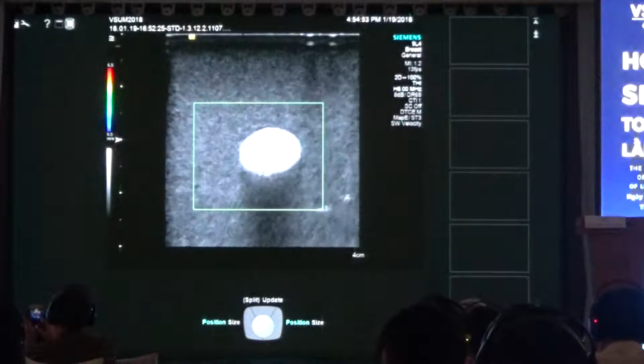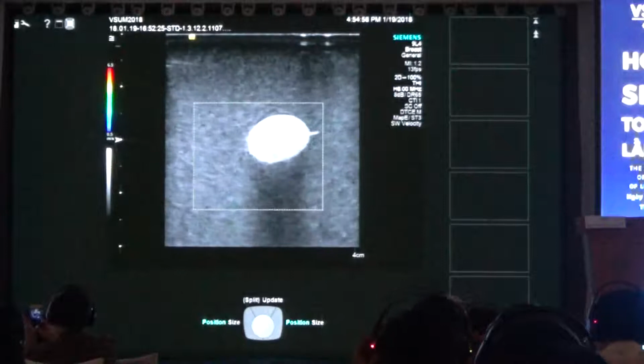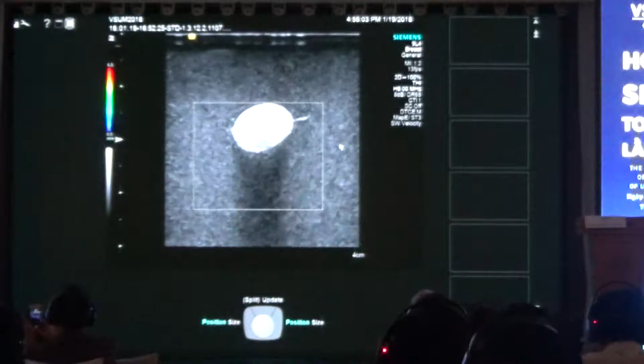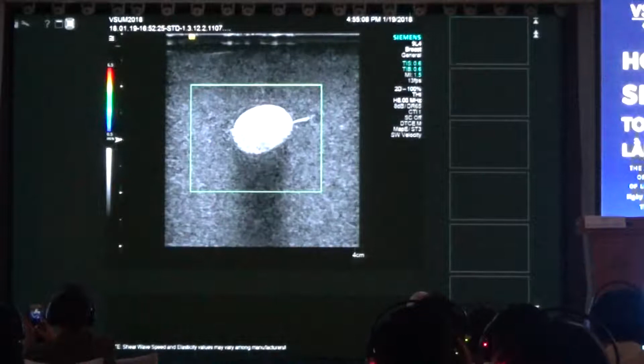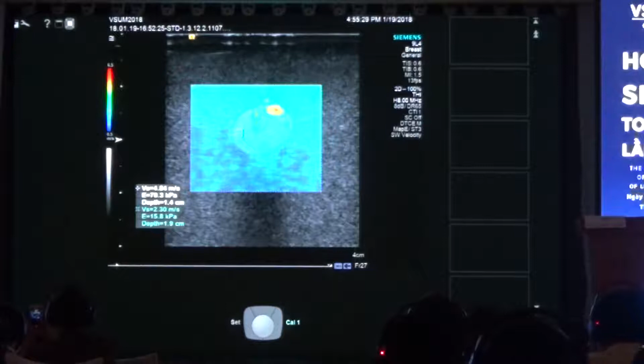Another problem we can have is if you don't apply uniform pressure. So what I'm going to do is on the right side of the image, I'm applying more pressure. So we call it heel and toe, the transducer. So I'm putting a lot of pressure on one side and no pressure on the other. And when we do our 2D shear wave, you can see that the left half where I'm applying more pressure is again very stiff, almost 5 meters per second, where on the other side where I'm applying less pressure is only 2.3. So we can make huge differences by applying inaccurate pressure.